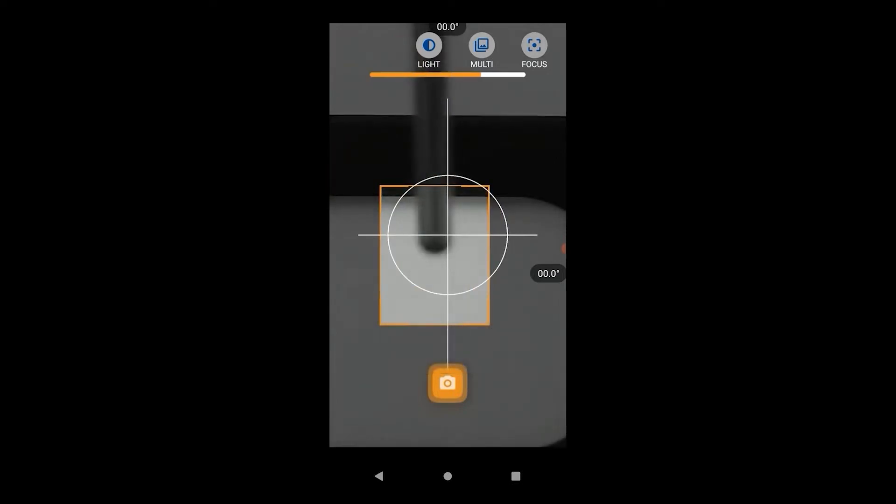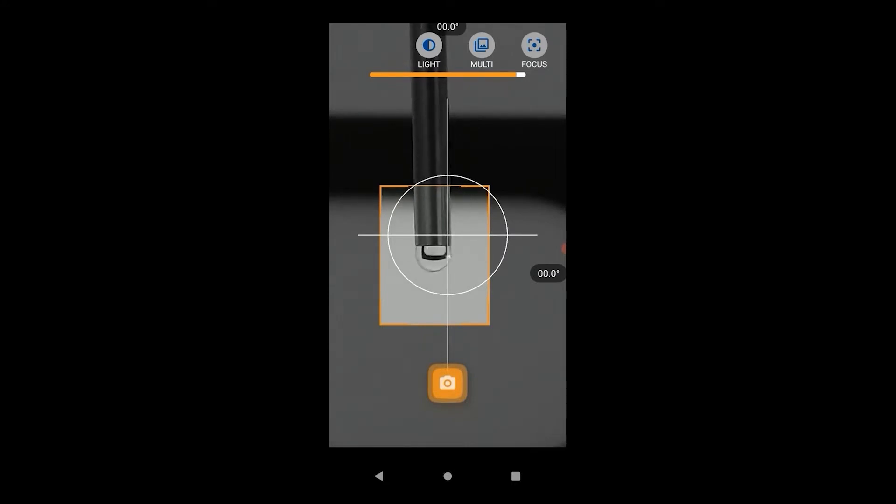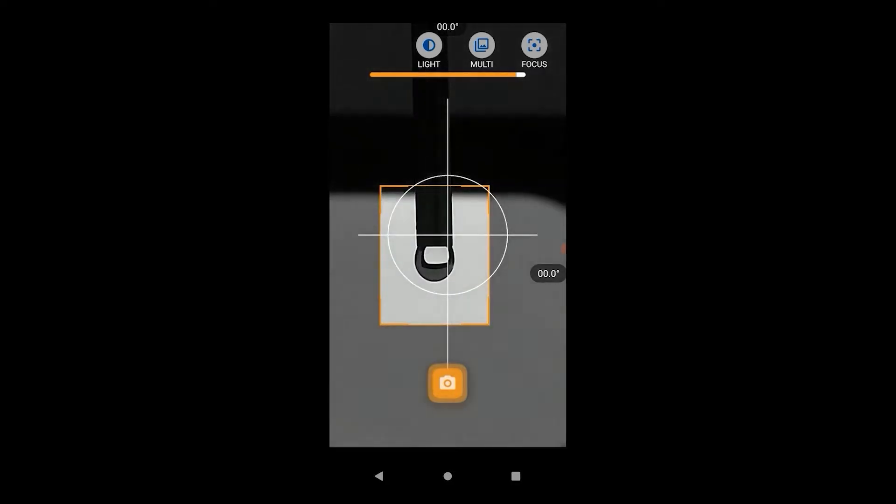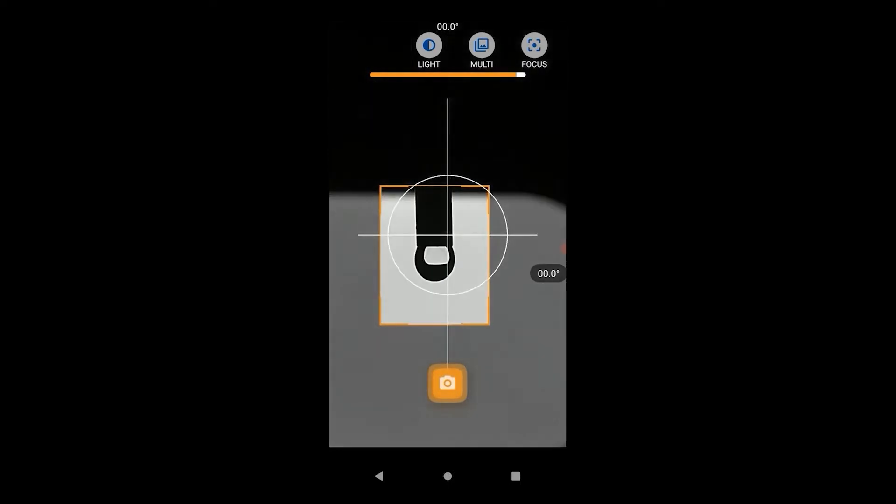Generate a droplet as a reference. Use the focus slider to focus on the droplet to get the best results. The focus slider should ideally be as close to the maximum value possible. The aim is to be as close to the droplet as possible without losing focus.